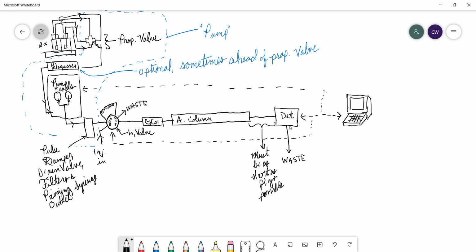Then we go into the detector, and from the detector we go to waste. Sometimes you can go into fraction collection. There are automatic fraction collectors out there that will take the UV vis absorbance, and it will use that to trigger fraction collection. Okay, and all of these things are interfaced via data lines that I've shown here in dashed lines to a PC. Okay.